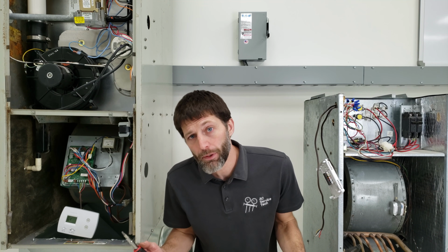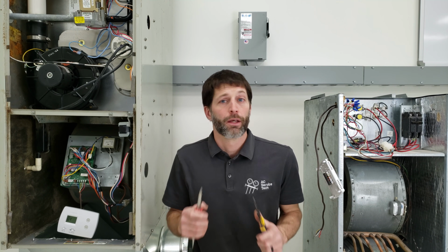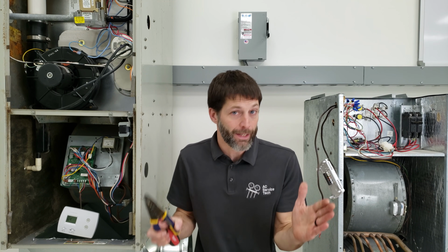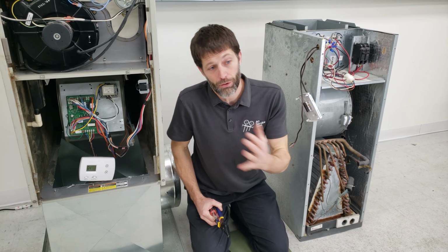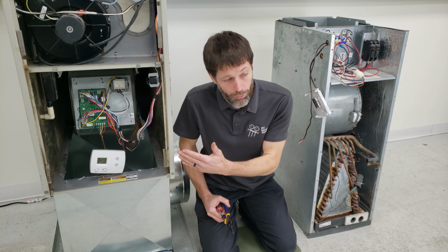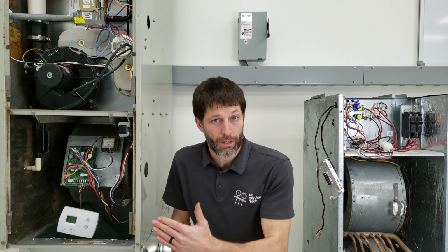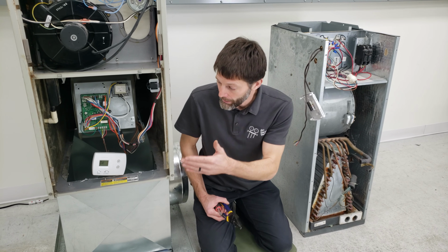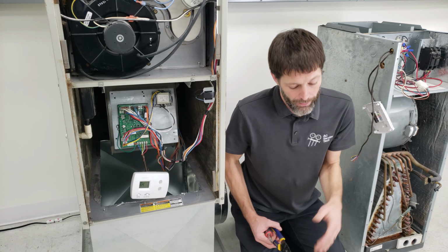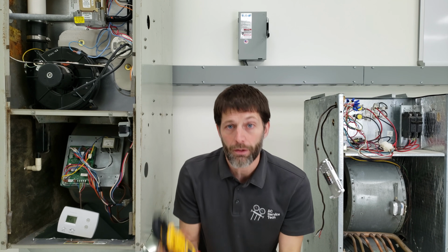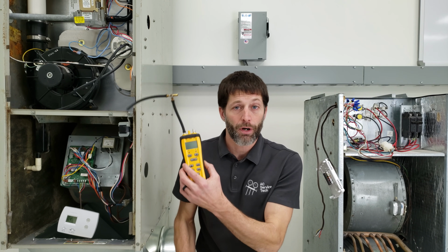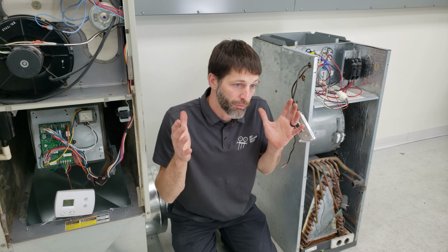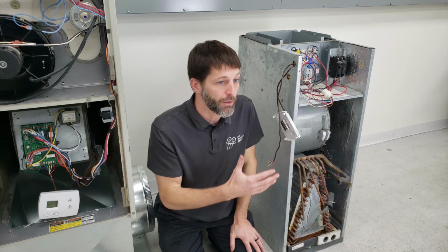So when it comes to intermittent problems with HVAC equipment, the rule is you got to make sure to do something. So if you have no leads, maybe the building owner doesn't tell you what's wrong and you don't see any status codes flashing, you kind of need to cycle the system, turn it off, check the electrical connections, crimp the connections, check the operation, all of that type of thing. You want to have a good multimeter, and you want to have a good water column manometer with a T for furnaces.